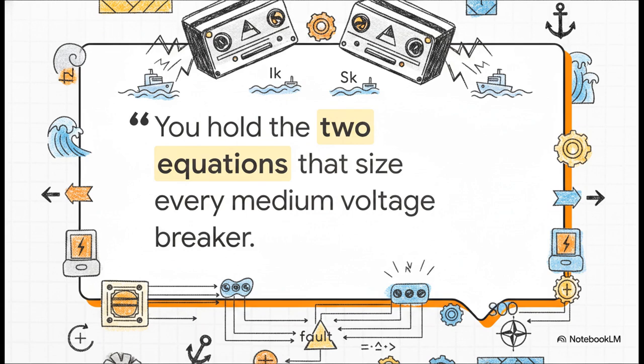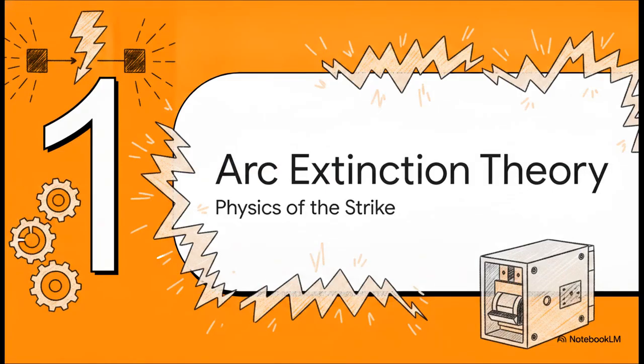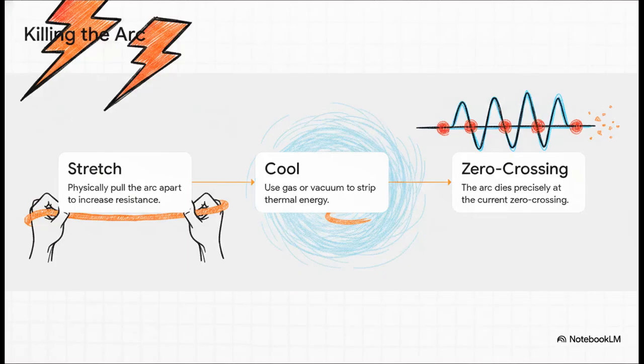But how does the breaker actually execute that survival in the real world? Let's move on and see how this builds as we get into arc extinction theory and the actual physics of the strike. So imagine the contacts flying apart. The current doesn't just politely stop flowing. Oh no, it rips through the air, ionizing gases and creating a superheated plasma arc that bridges the gap between those separating metal contacts. To kill this arc, the breaker has to do 3 things in a fraction of a second.